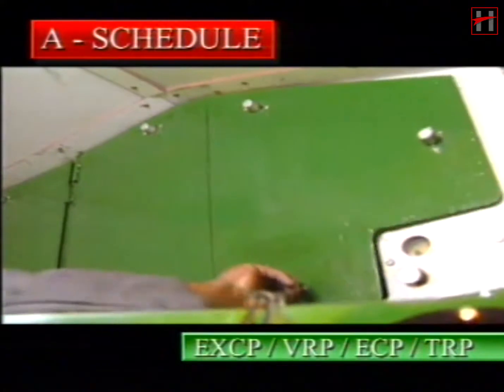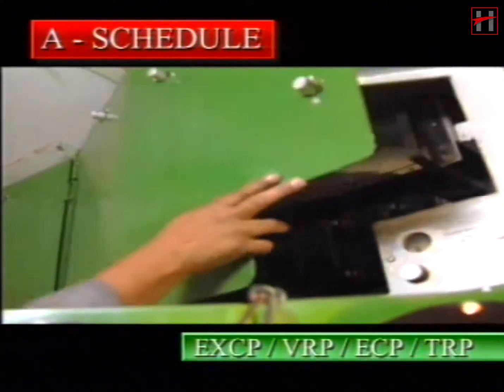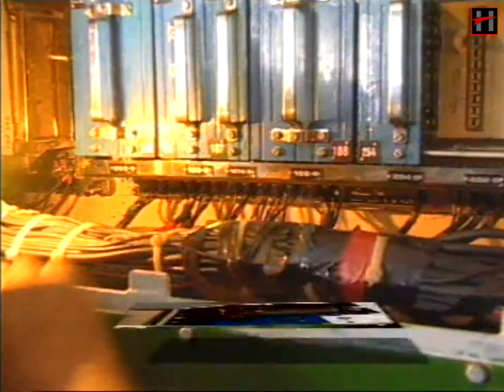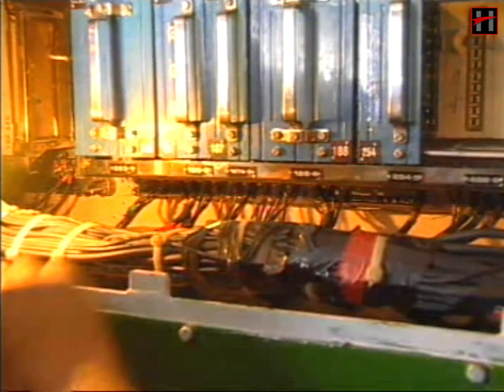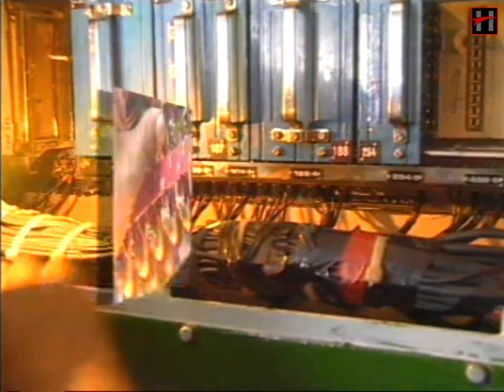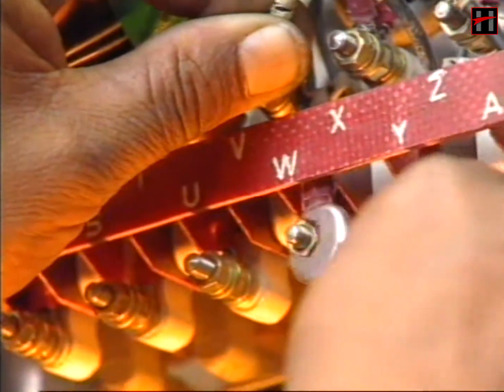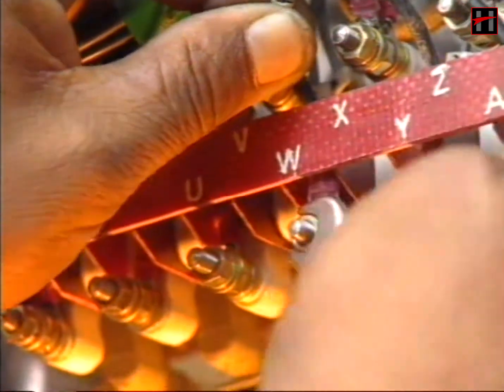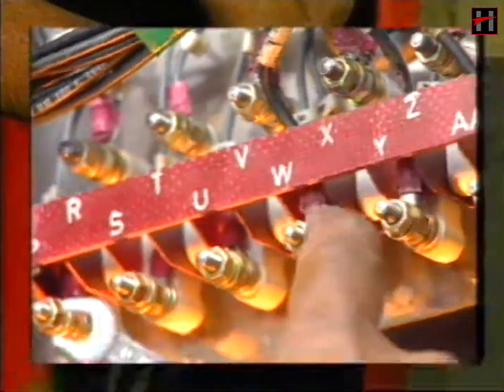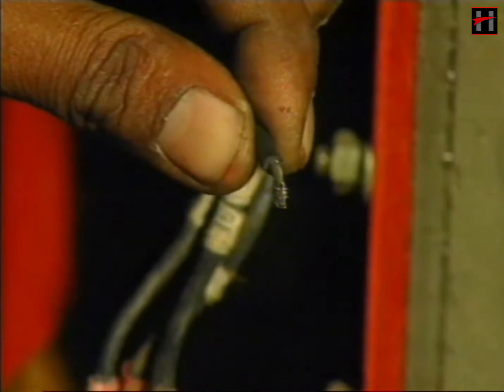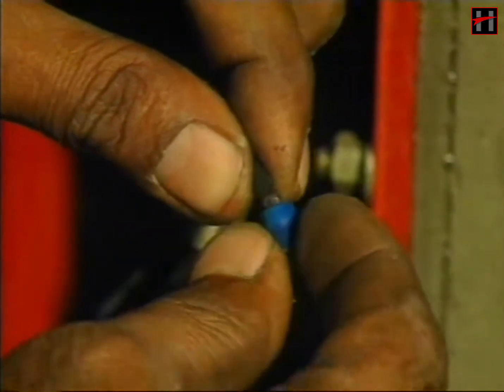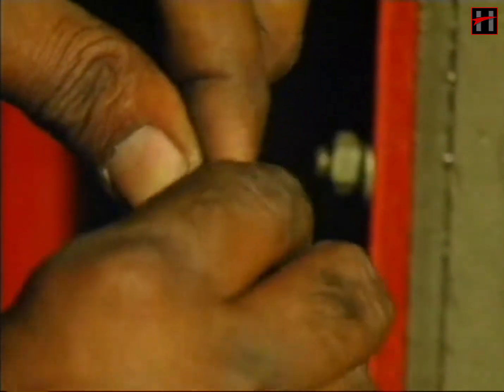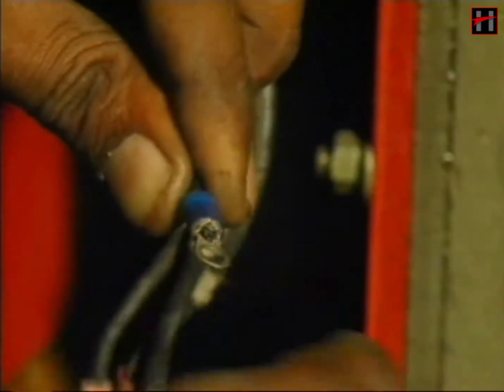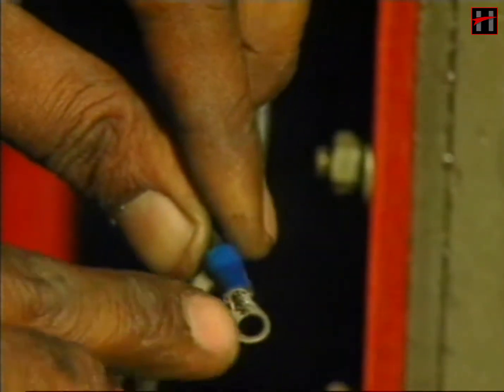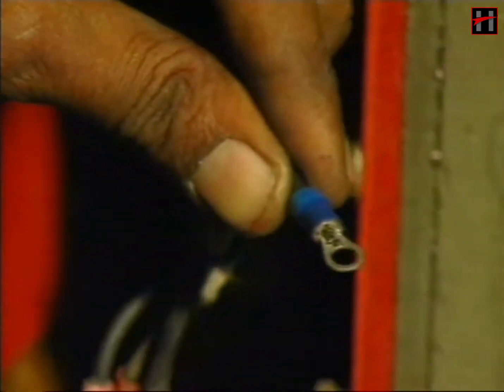In the A schedule, visually check the terminal connections of all the components and terminal boards of the panel. All the terminal connections should be completely tightened. If any signs of overheating is observed on terminals or thimbles or the terminal board, replace the thimble or the terminal board and trace out the cause of overheating.